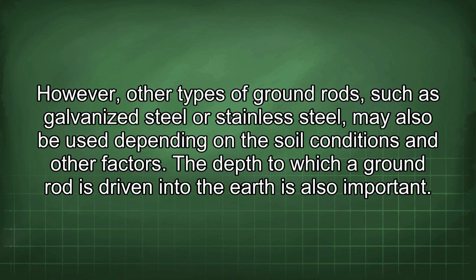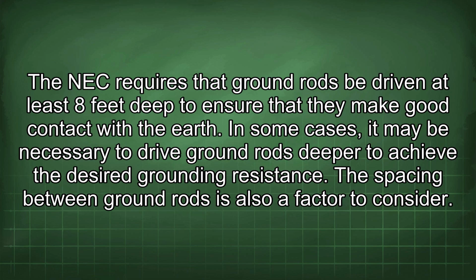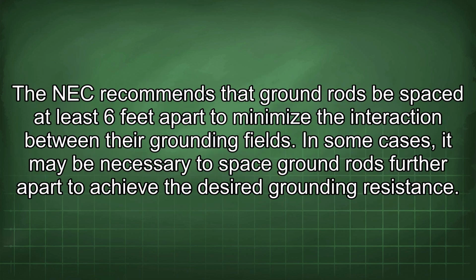The depth to which a ground rod is driven into the earth is also important. The NEC requires that ground rods be driven at least 8 feet deep to ensure that they make good contact with the earth. In some cases, it may be necessary to drive ground rods deeper to achieve the desired grounding resistance. The spacing between ground rods is also a factor to consider. The NEC recommends that ground rods be spaced at least 6 feet apart to minimize the interaction between their grounding fields. In some cases, it may be necessary to space ground rods further apart to achieve the desired grounding resistance.